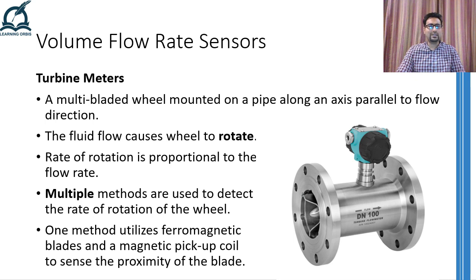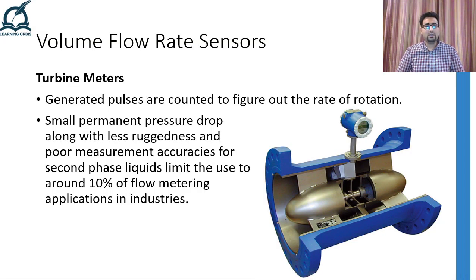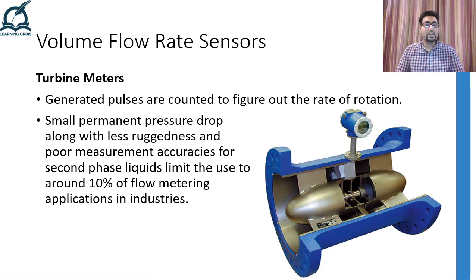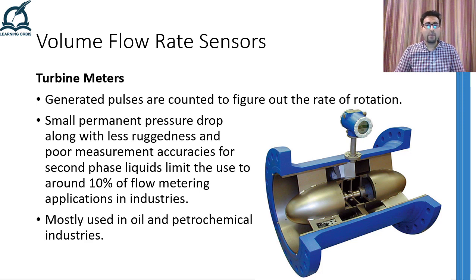Methods other than magnetic proximity sensors can also be employed to sense the rotation of the wheel. For example, some forms of turbine meters utilize fiber optics to sense the light reflected by the turbine blades, hence generating an output whenever a reflection is received. The downsides of turbine meters include a small amount of permanent pressure drop induced into the system, along with the turbine blades being prone to corrosion and wearing due to the fluid rubbing against them. Furthermore, the accuracy of turbine meters drops considerably if it has been calibrated for a pure liquid and is being used to measure the flow rate of liquids that contain another insoluble liquid, for example water particles present in oil. Turbine meters find most of their applications in oil and petrochemical industries.